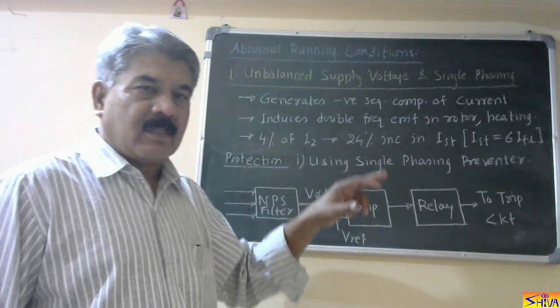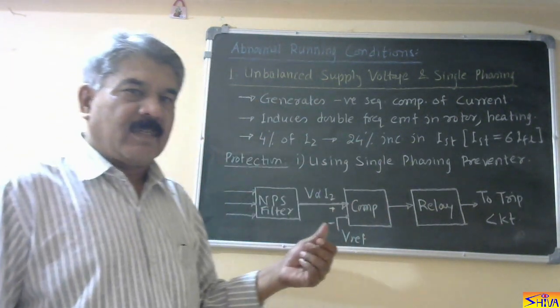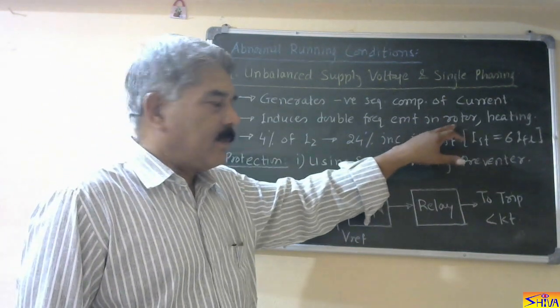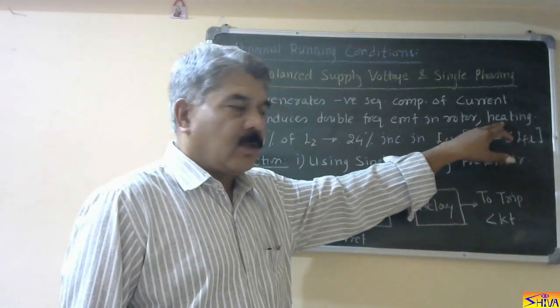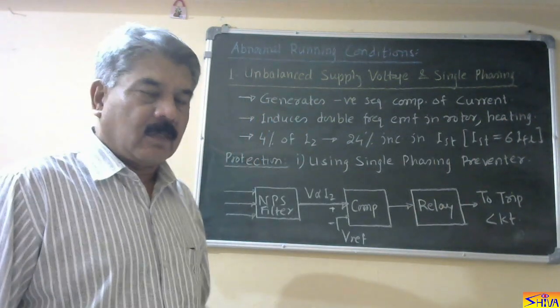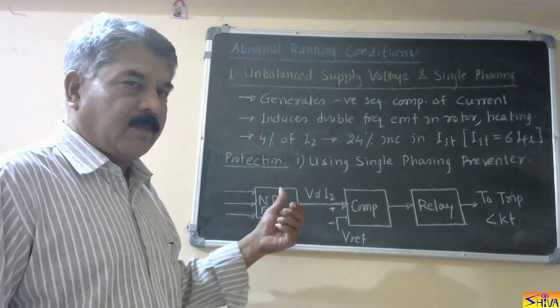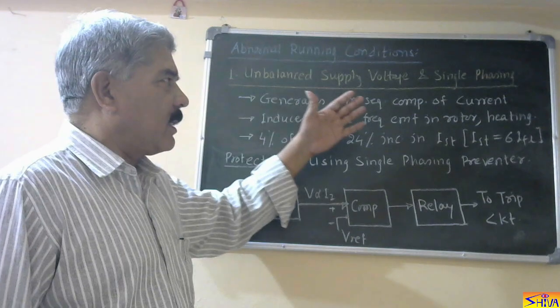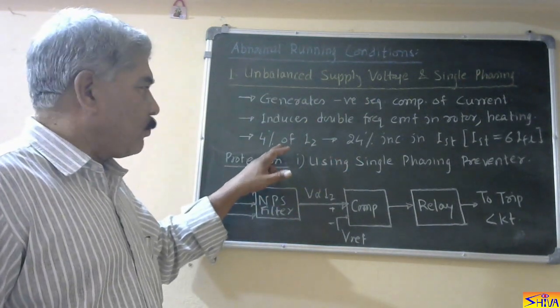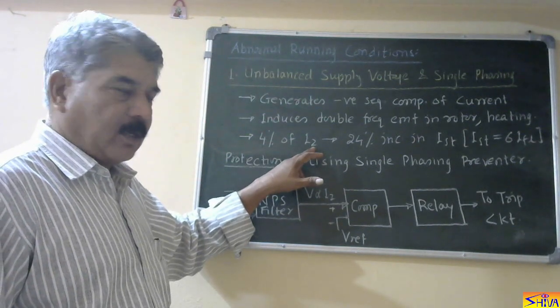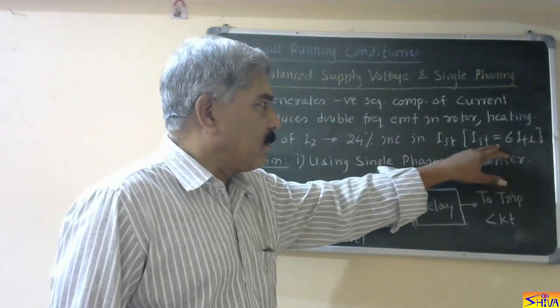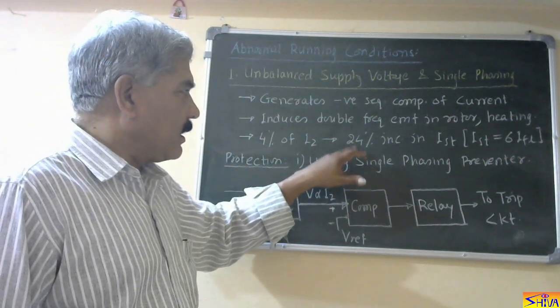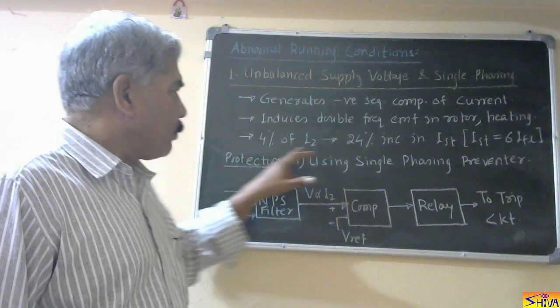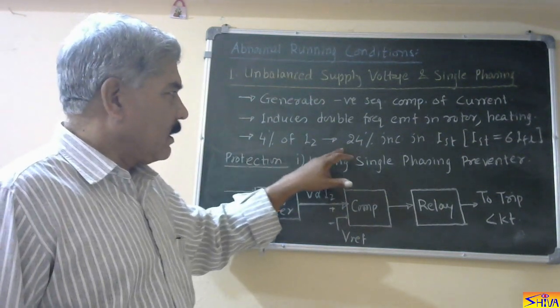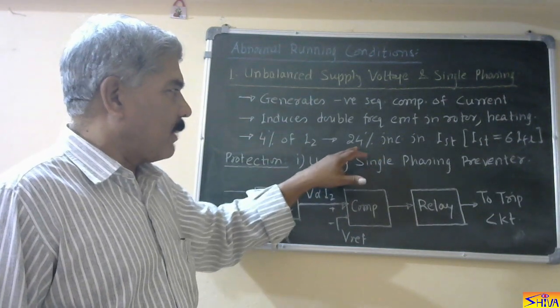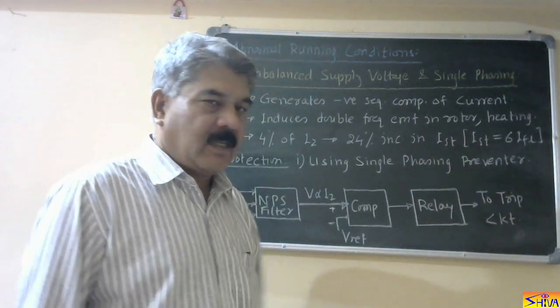Now this negative sequence component of the current induces double frequency EMF in the rotor, and due to this double frequency EMF, heating of the rotor starts. That is the effect of the flow of negative sequence current, which is the effect of unbalanced supply voltage and single phasing. Suppose there is 4% negative sequence component of the current. Then, assuming starting current is 6 times full load current, this increases the starting current by 24%.